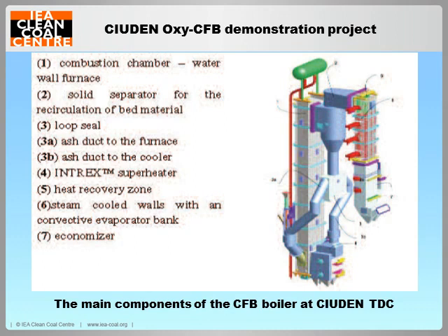CIUDEN Technology Development Center has a 30 megawatt thermal Oxy-CFB boiler. The main components of this boiler are shown here. The main focus of the project is to support and validate the scale-up of Foster Wheeler's Flexi-Burn CFB technology, which will be the basis for a 300 megawatt Oxy-CFB project, which is called the Compostilla Oxy-CFB 300 project. The CIUDEN CFB unit was commissioned in September 2011. Tests have been carried out since then.